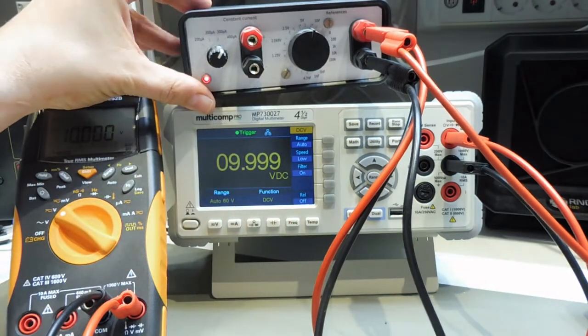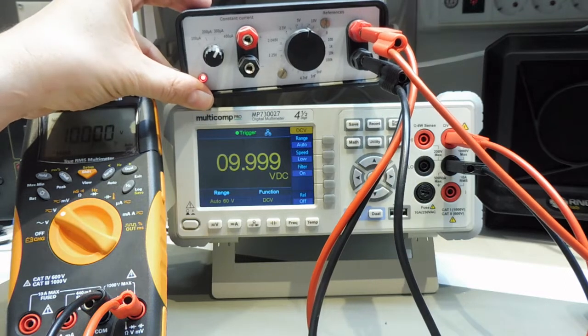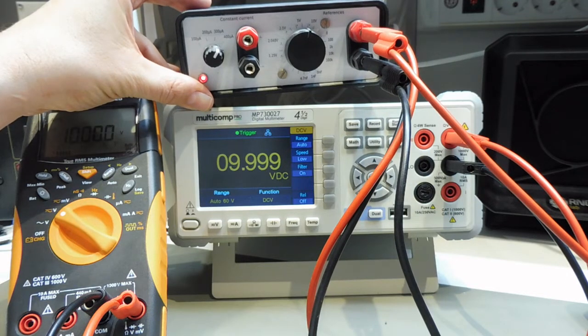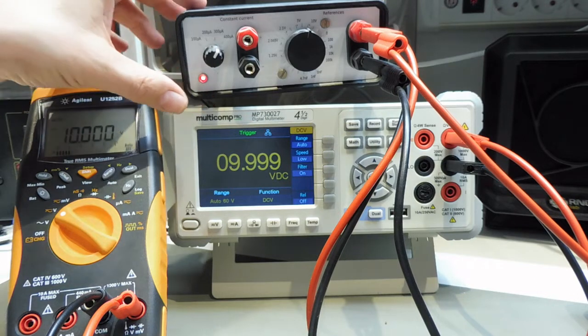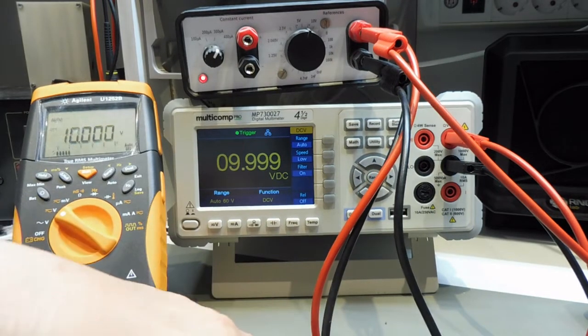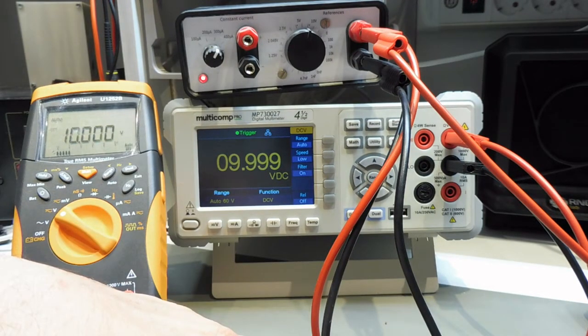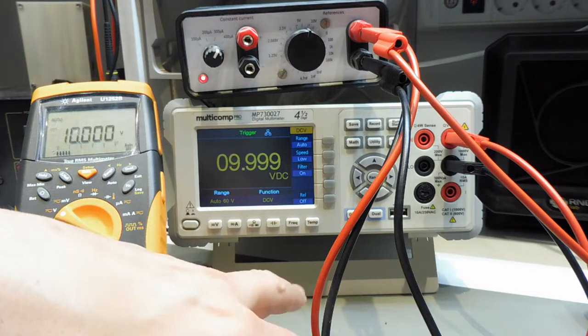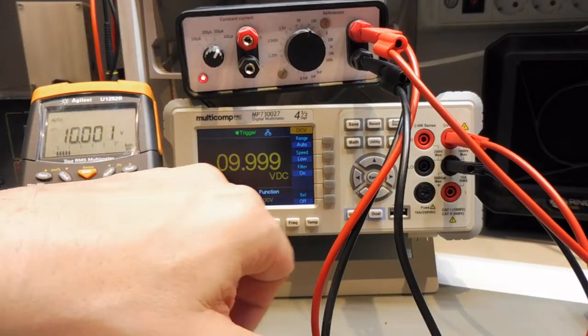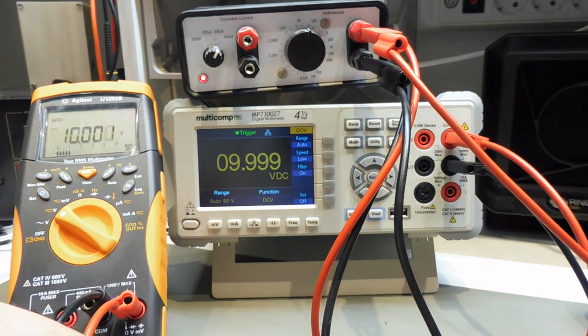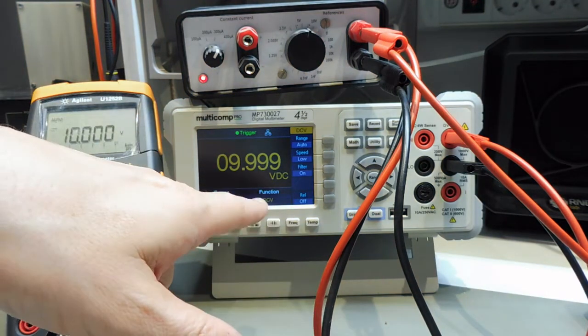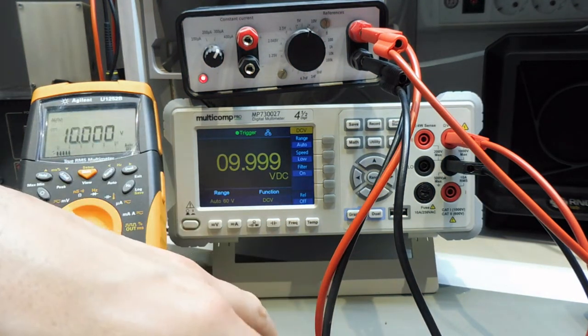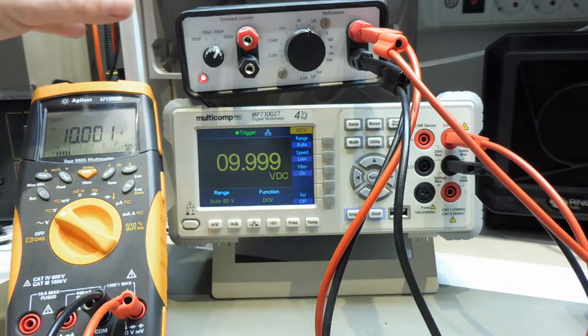The voltage references are not selected for absolute long-term stability; there are much better ones for that. But I selected them for their initial reference, and the most precise one is the 10 volt reference, which is accurate to 0.01%, even a bit better than both of these meters here. I'm using them to verify that my meters are still within specification.